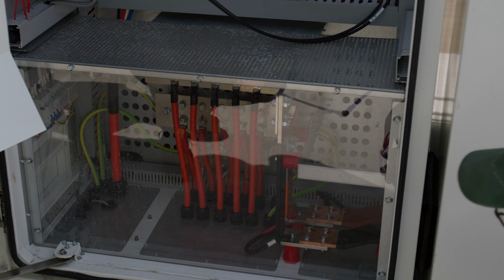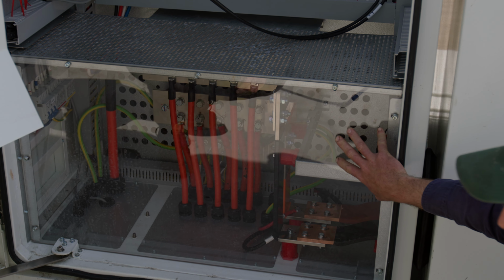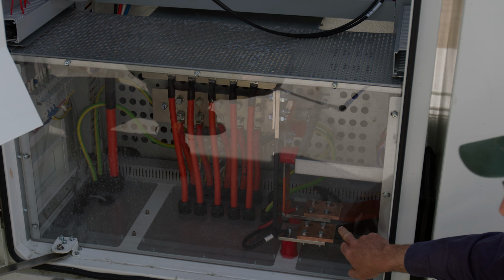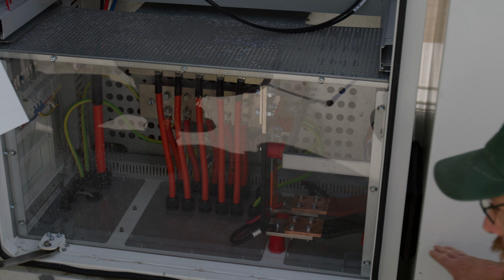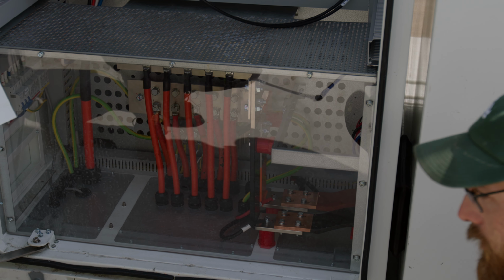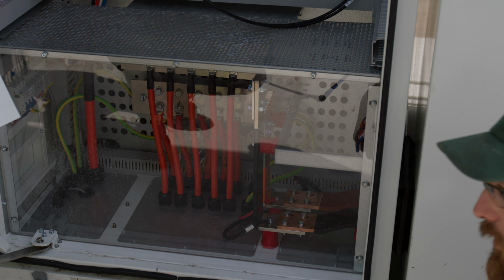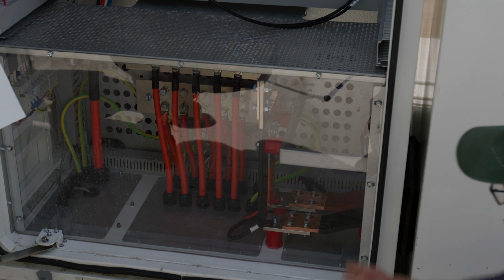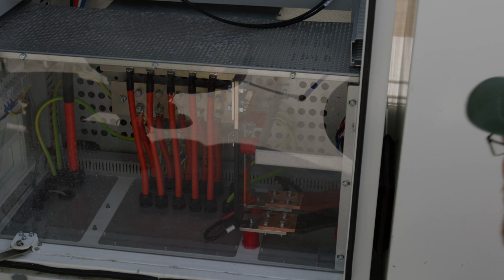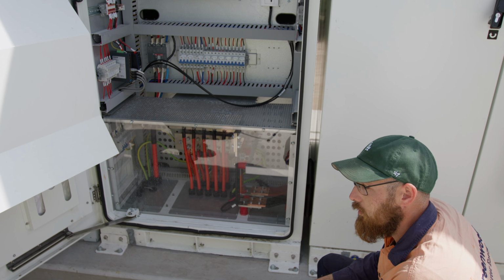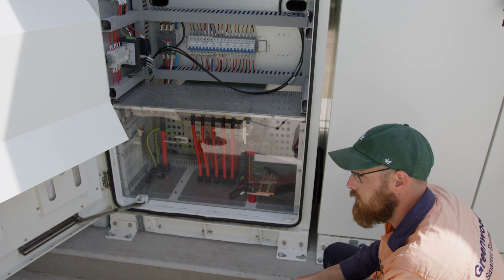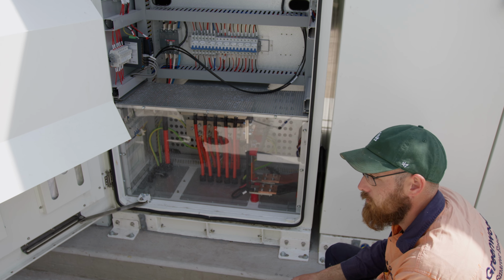The way that this battery connection panel connects to the batteries is via a 100mm busbar that goes directly from chamber to chamber, all the way along the bottom. Oh, so there's an unbroken busbar going all the way through. All the way through. So it goes from here down 3 cabinets, all through each battery. And basically there's a hole in the side of the cabinet.